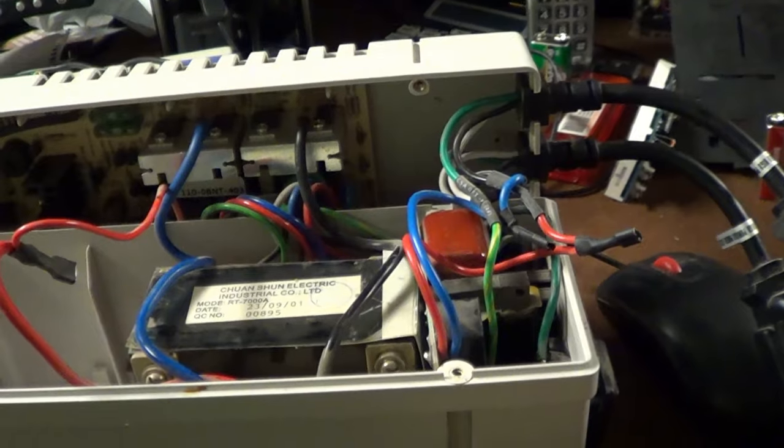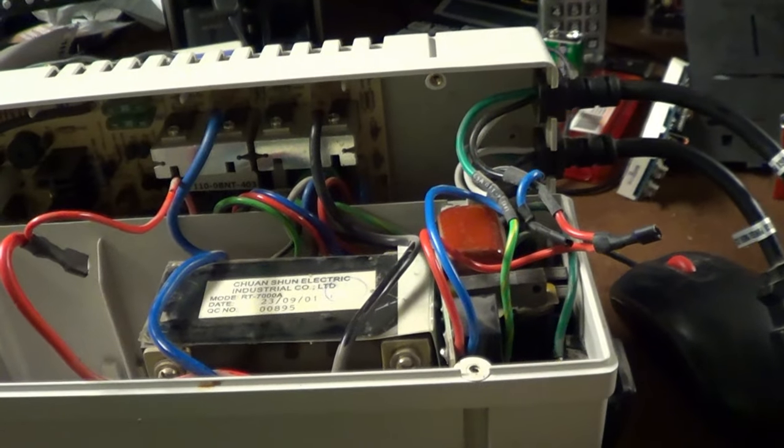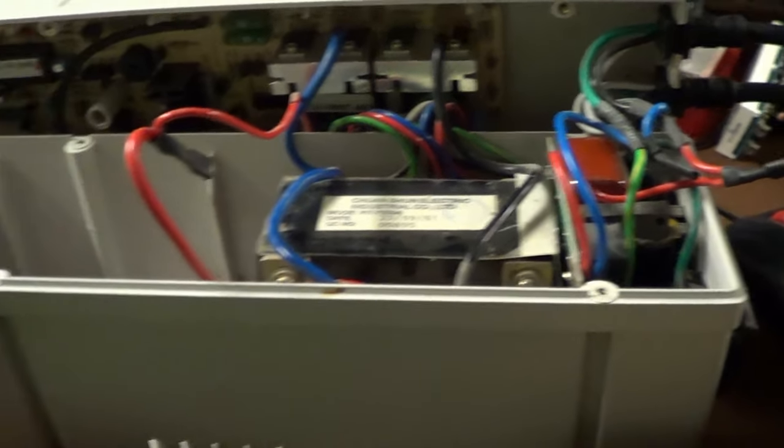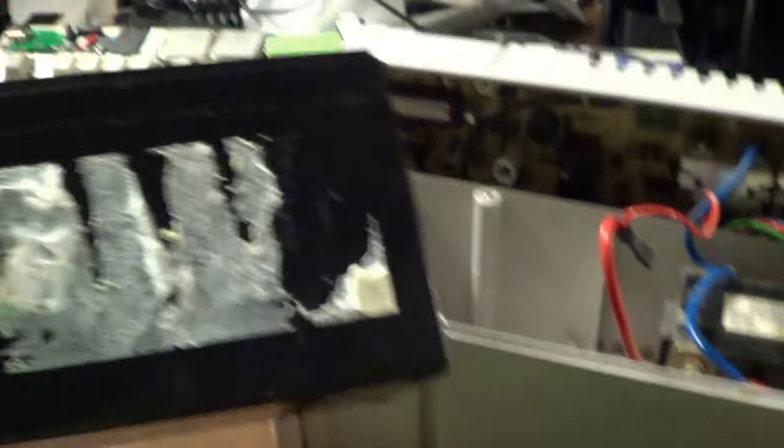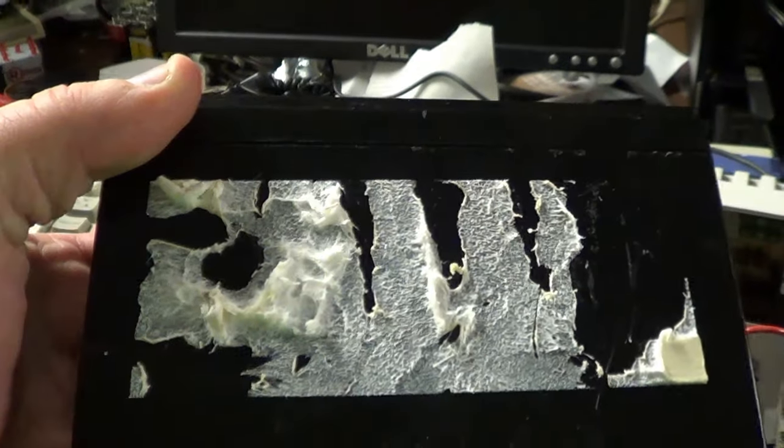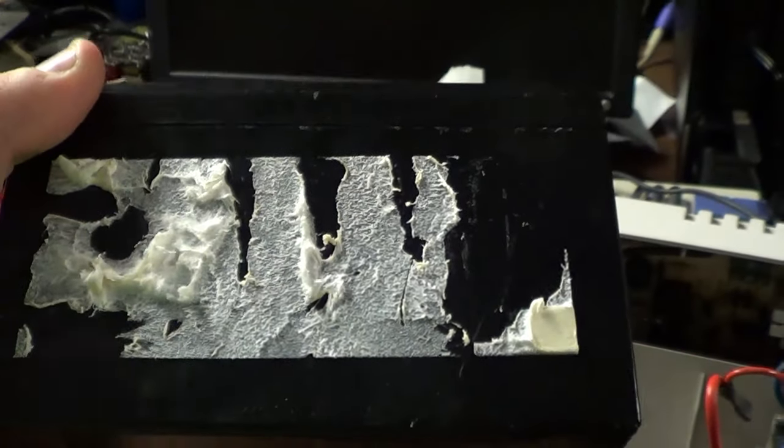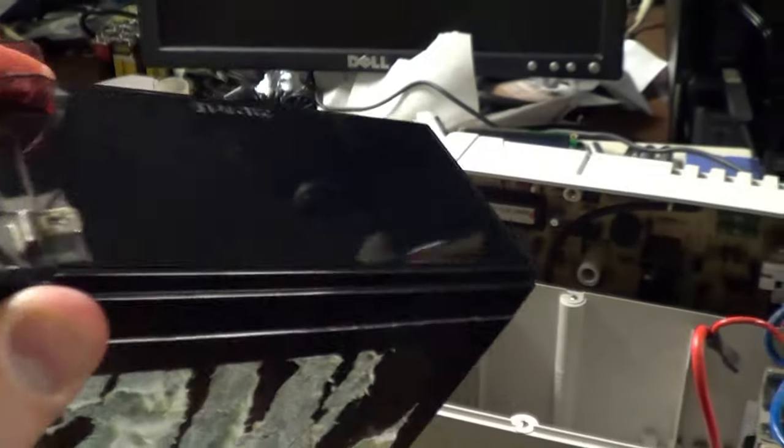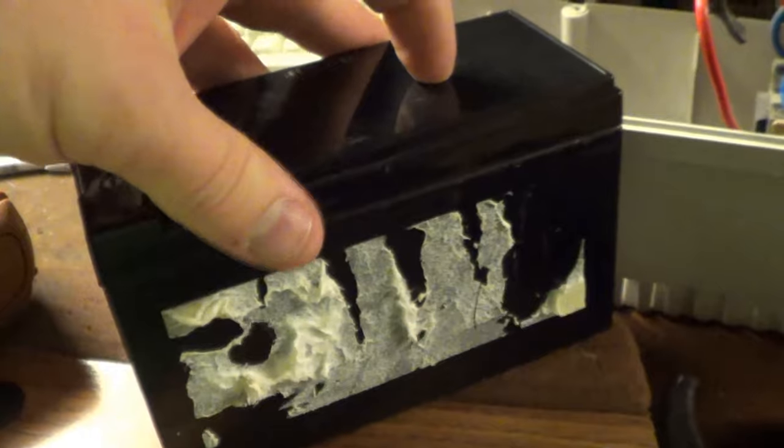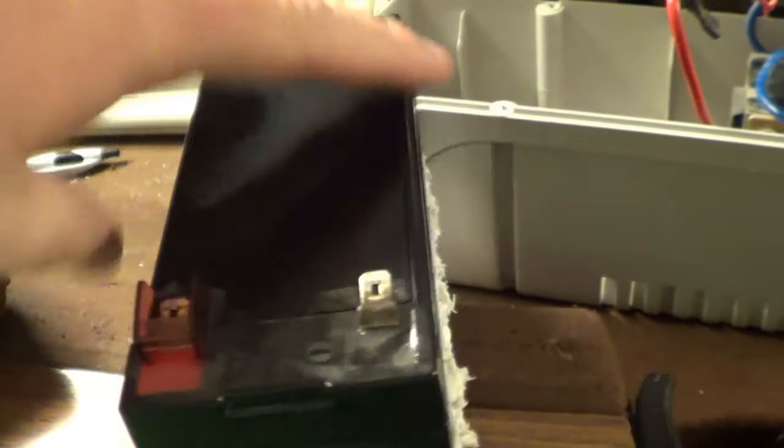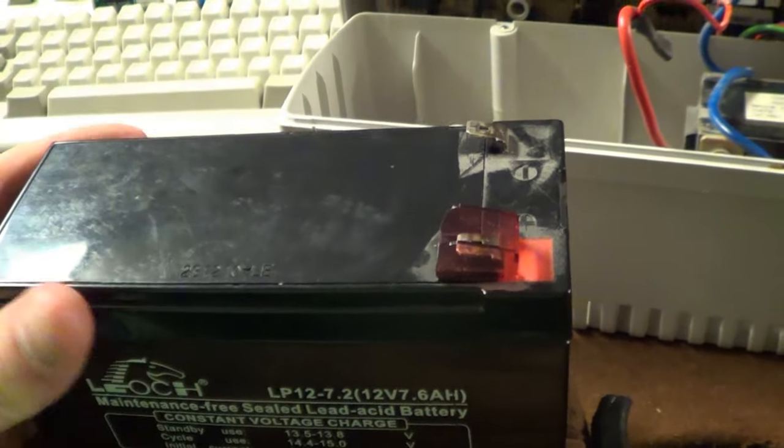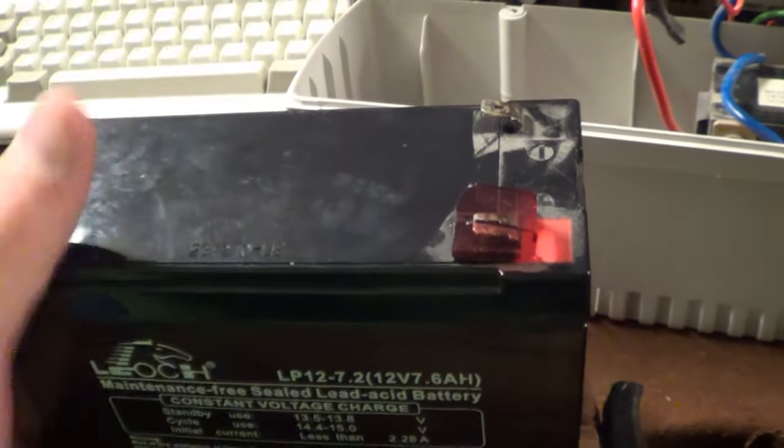In my defense, as I said previously, I'm not the first person who has been inside this UPS. Someone definitely replaced this battery, and I can't help but think that it probably wasn't new when it was put in. I think this was probably taken from something else. Here's the date code on the battery, whether that's the 23rd of December 2010, or the 23rd of October in the year 2012, I'm not entirely sure. I tend to lean toward the first interpretation that it was December 23rd of 2010 when this battery was manufactured, and it looks like it was glued to another, probably from a UPS having much larger capacity, maybe a unit that even failed.